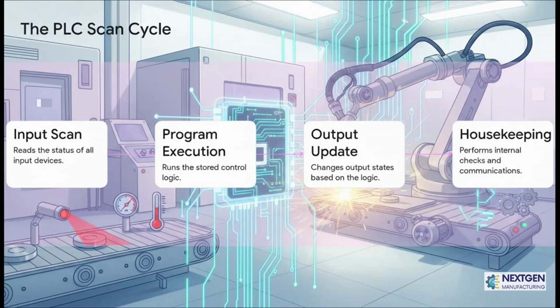So how does this little brain think? Well, the PLC runs on a continuous, high-speed loop called the scan cycle, and it happens in just milliseconds. First, it reads all the inputs from the sensors. Then it runs through its programmed logic, and finally, it updates all the outputs to the actuators. It just repeats this cycle, read, think, act, over and over, thousands of times a minute.